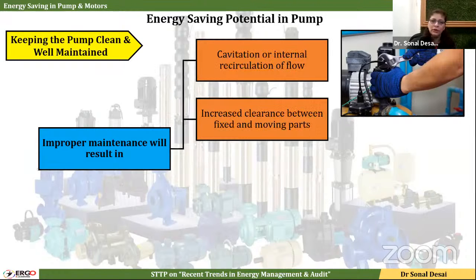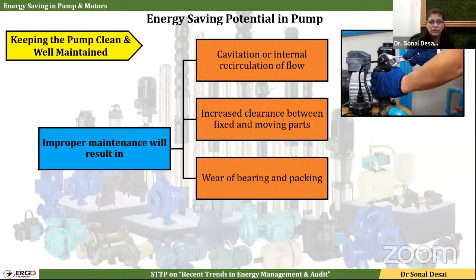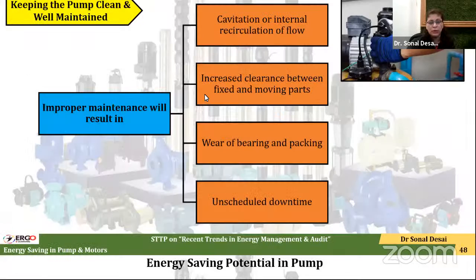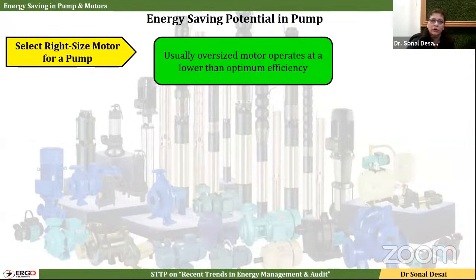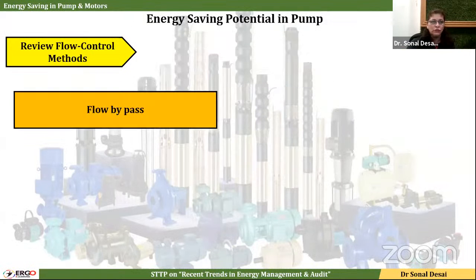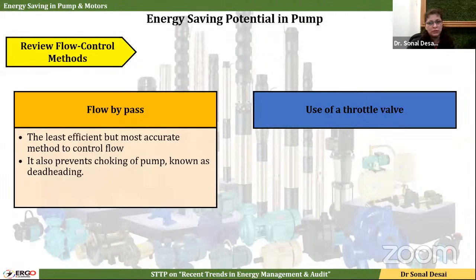So that will help to reduce cavitation. If there is cavitation, there will be increased clearance between fixed and moving parts. There will be wear and tear. Then select the right size motor. Many a time this is neglected. The pump is properly sized, but the motor is oversized. So that inefficiency will also be added to the pump working cost. Review the flow methods we have already discussed. So I'm skipping this portion.